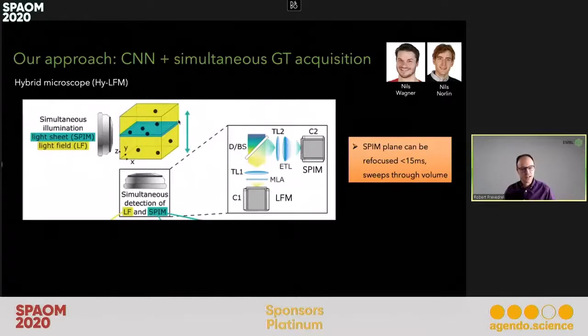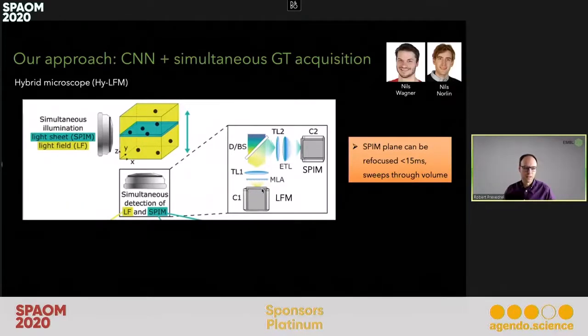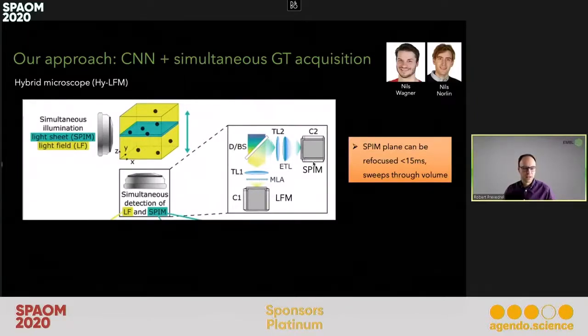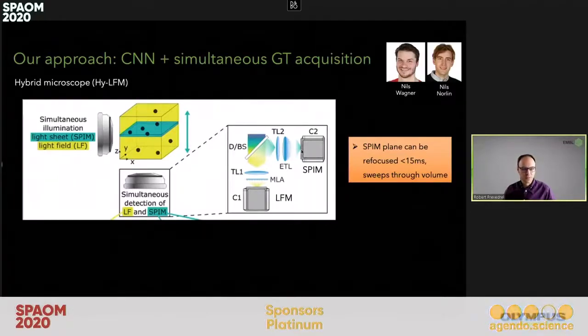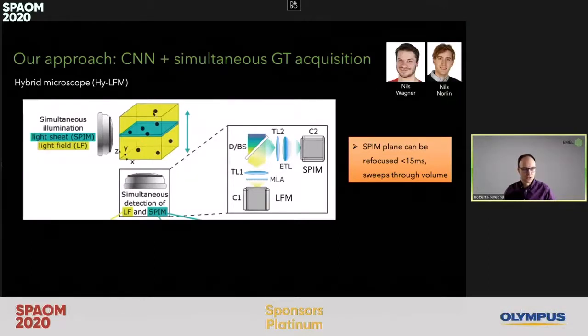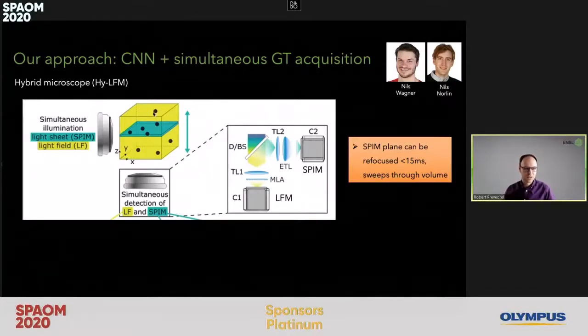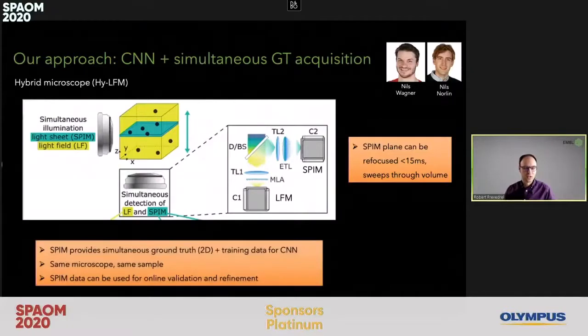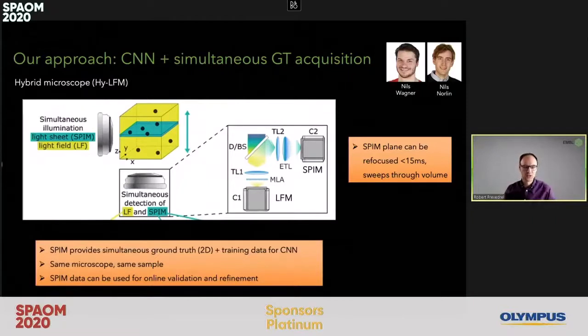In this hybrid microscope, we illuminate from the side. We can illuminate either the whole volume and detect it via microlens array on our light field camera, or simultaneously illuminate a single plane and image this with a light sheet camera, then quickly reposition the focal plane in detection. Also, using galvanometric mirrors, we can reposition the excitation plane in the volume. This hybrid microscope, which we term Hy-LFM, allows us to get simultaneous information about ground truth at high resolution in 2D.